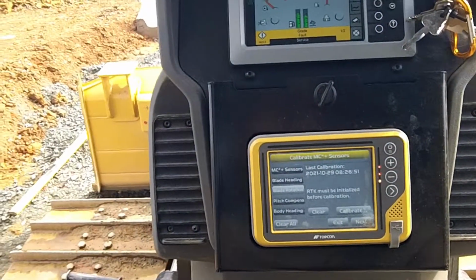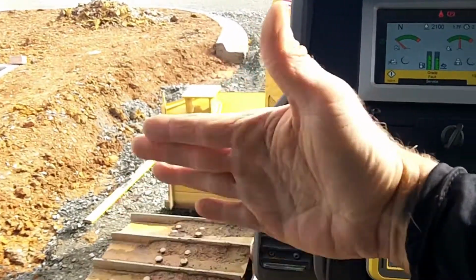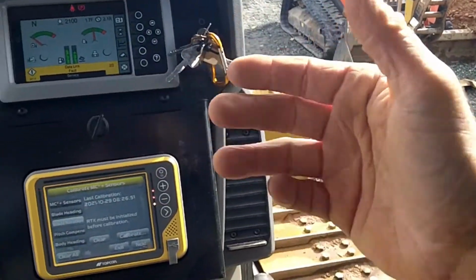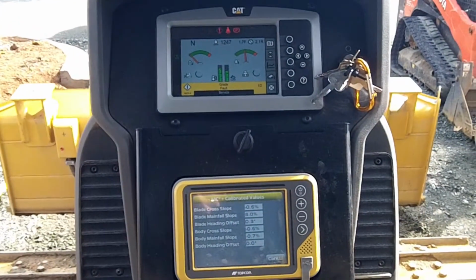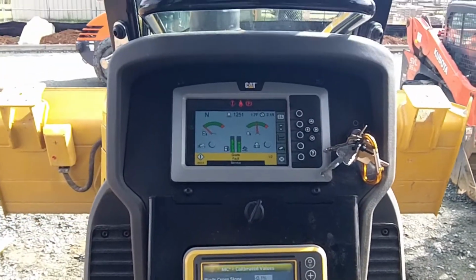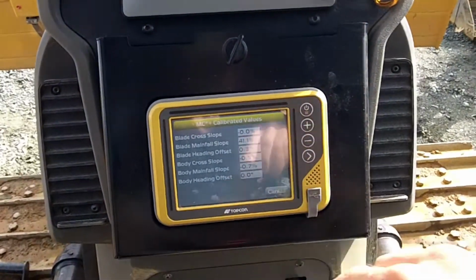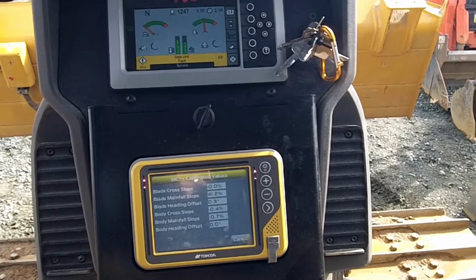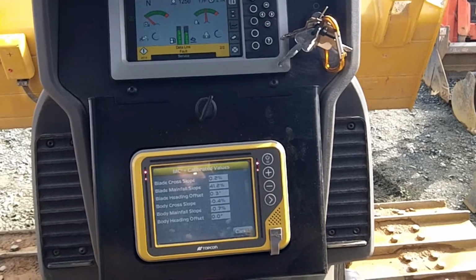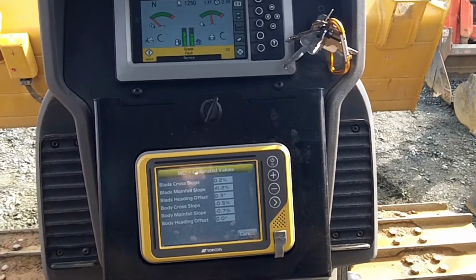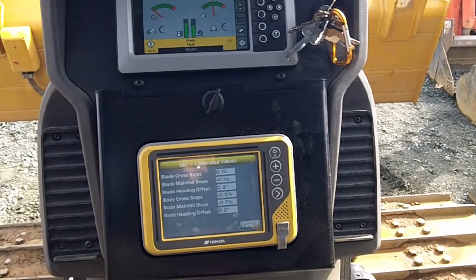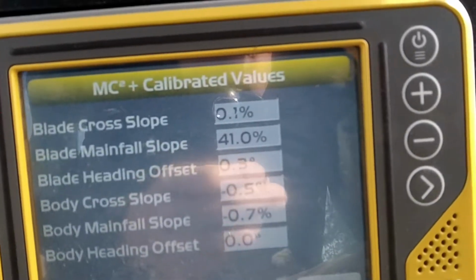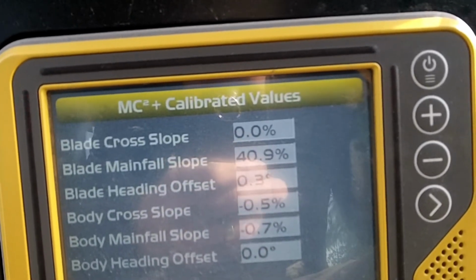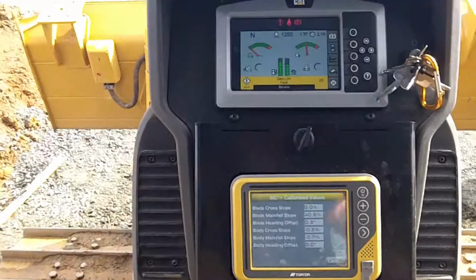That does the limit of the sensor, it's maximum. Now that calibration is done for the blade, let's just bring it up, raise it all the way up, get that to 0. And it was on 0, I just moved it a little bit. There we go, and just go double check.